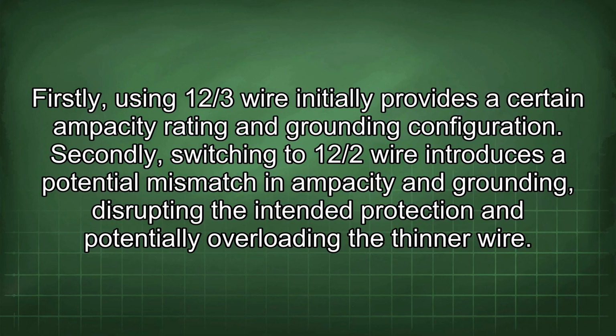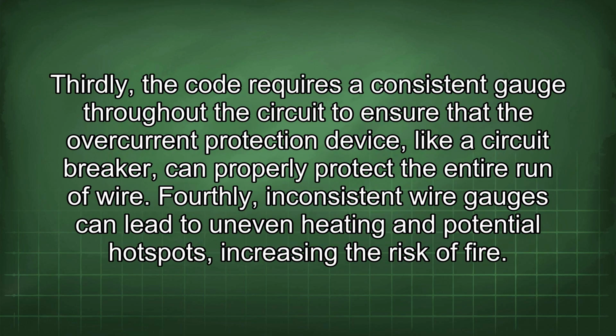Secondly, switching to 12/2 wire introduces a potential mismatch in ampacity and grounding, disrupting the intended protection and potentially overloading the thinner wire. Thirdly, the code requires a consistent gauge throughout the circuit to ensure that the overcurrent protection device, like a circuit breaker, can properly protect the entire run of wire. Fourthly, inconsistent wire gauges can lead to uneven heating and potential hotspots, increasing the risk of fire.